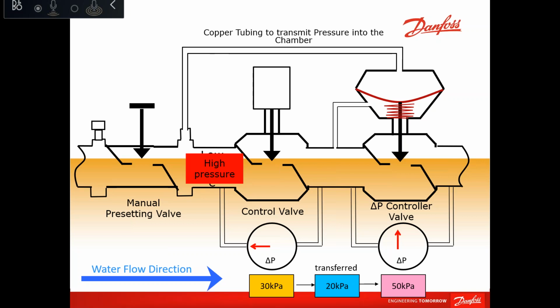Okay. Will the ABQM be able to prevent the overflow if the pumps are running at too high a speed due to poor pump control? Yes. If the overall pressure of the system is higher than the requirement, the PICV will be able to give you your design flow up to 6 bar dynamic pressure. The maximum differential pressure is 6 bar. So if the pump head is 6 bar and you have the pump running against one PICV, the PICV should be able to give you your design flow.